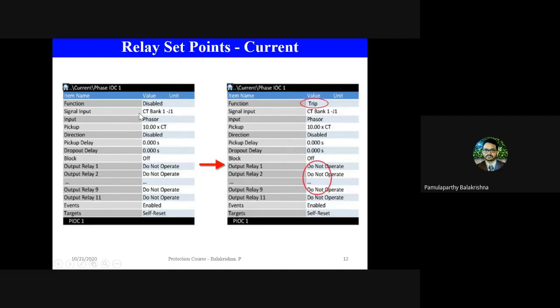Okay. So the first one is the function. Function here refers to phase instantaneous overcurrent, and it comes under the current category. This can be either enabled or disabled. When you say disabled, it means that this function will not execute, even if the overcurrent condition occurs. It will not do any action. In order to make it work, you need to configure something like trip the breaker. When any overcurrent occurs, you just trip the breaker.